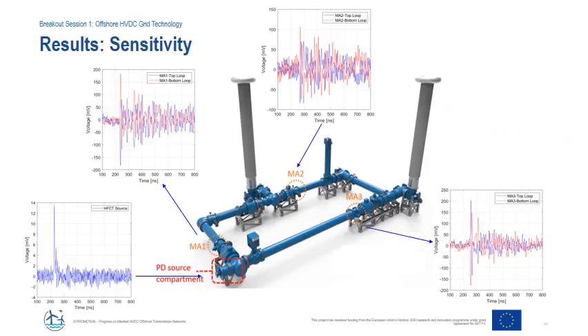The results also highlighted the lower attenuation of the PD signal in the low frequency range where the magnetic antenna works. From the graphs, it can be observed that the antennas at position 1 and 3 had almost the same amplitude despite the very different propagation path of the signals. At position 2, the amplitude of the signal in fact decreased to half. Although the charge estimation from this antenna might have a higher error, its peak amplitude still makes the PD detection possible.